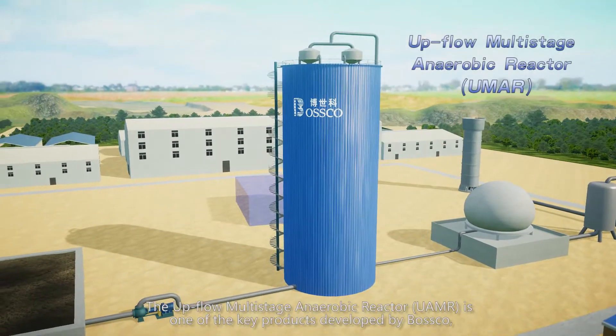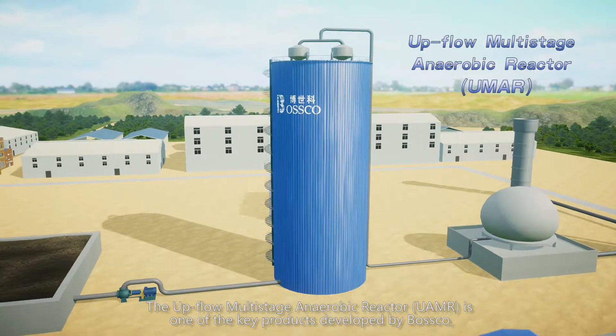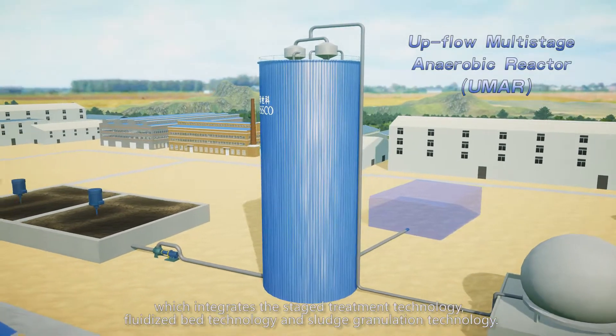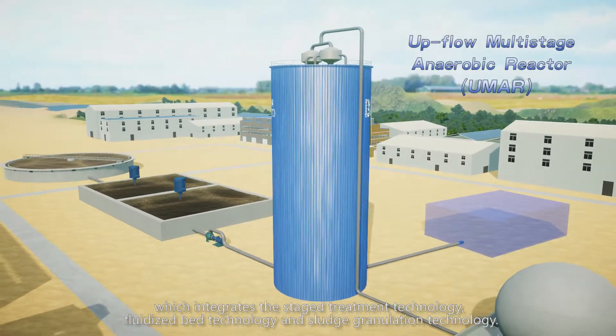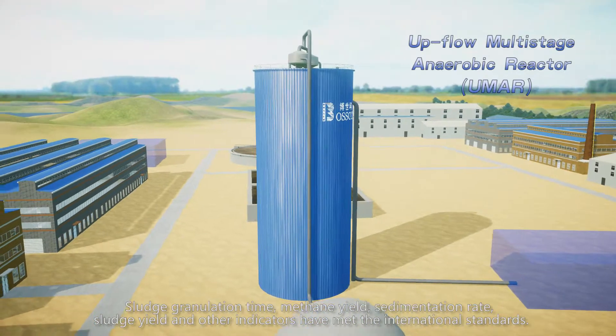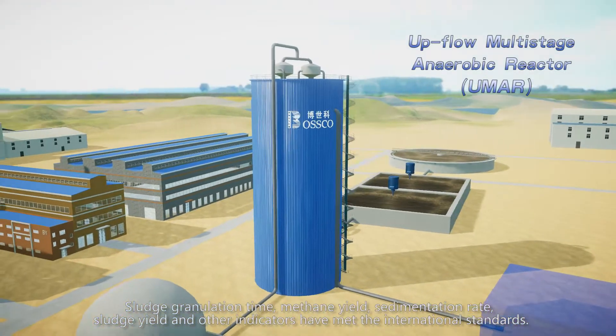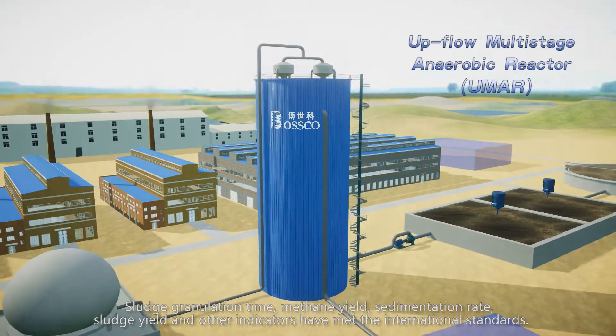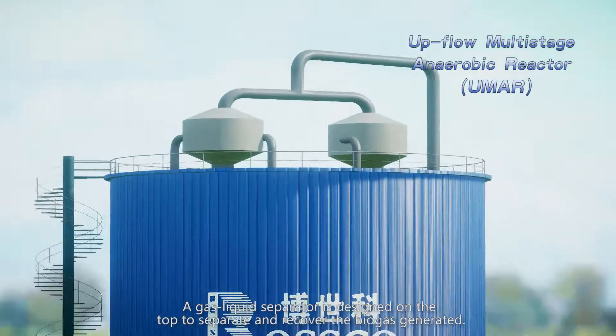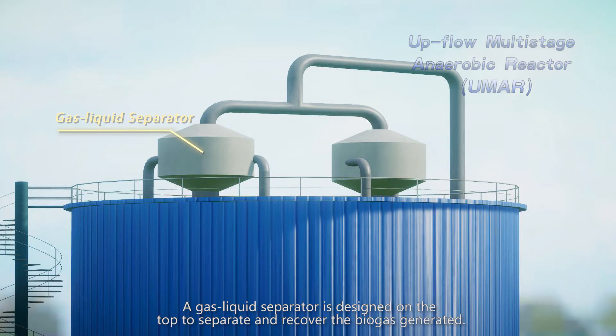The upflow multistage anaerobic reactor is one of the key products developed by Bossco, which integrates staged treatment technology, fluidized bed technology, and sludge granulation technology. Sludge granulation time, methane yield, sedimentation rate, sludge yield, and other indicators have met international standards. The two-stage treatment structure increases the impact-resistant capacity of the UMR and prevents sludge from backing and loss. A gas-liquid separator is designed on the top to separate and recover the biogas generated.